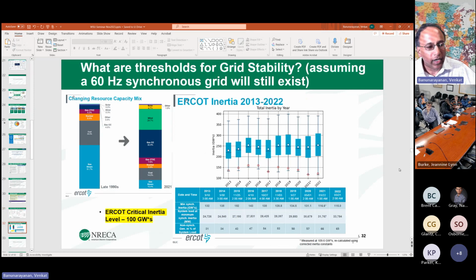So, and then finally, of course, the inertia. Assuming, and that's why I put this, assuming a 60 Hertz grid will still exist. I mean, we don't know that. It need not. There's no reason for the grid to be at 60 Hertz, or 50 for that matter. You can have it at any frequency, but nevertheless, this shows inertia in ERCOT and how it has reduced over the years as more and more non-synchronous generation has come in. It's not under any raising of alarm bells yet. They have an inertia level of 100 gigawatt-seconds. It's measured in gigawatt-seconds, essentially how many gigawatts you need for each second. That's synchronous generation.